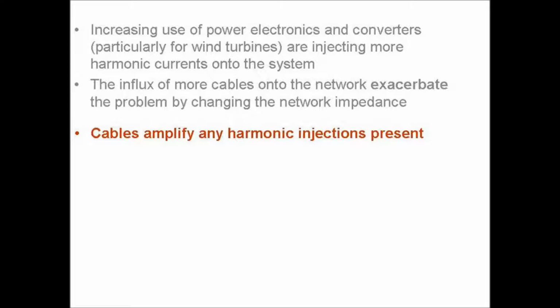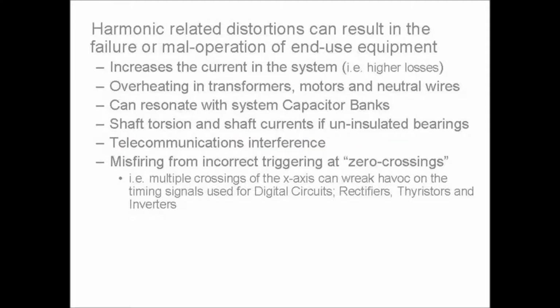So if you put a cable into a weak part of the network, it could be okay. But if you put a cable into a weak part of the network and there's harmonic currents there, it can cause all sorts of problems. So what does it mean? I suppose it doesn't mean anything unless you've got a problem and there's something interacting with something else. Otherwise you can get away with it for years.